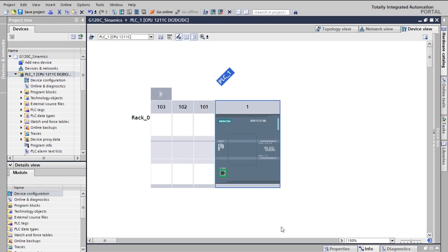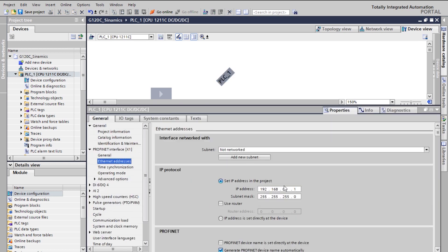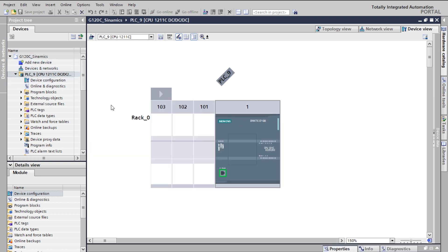Basically, what I'm going to do is control the G120C with the PLC. First, you need to select the properties — you can see the Ethernet options — and change the IP. I have configured my PLC with 192.x.x.19 because I have a network of PLCs. You also need to change the PLC name; mine is named PLC_9. Save this and you can see the name has changed in the project window.